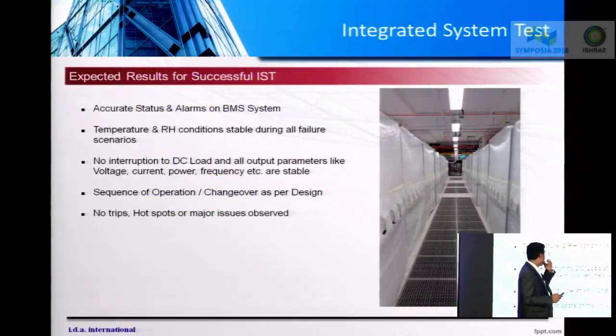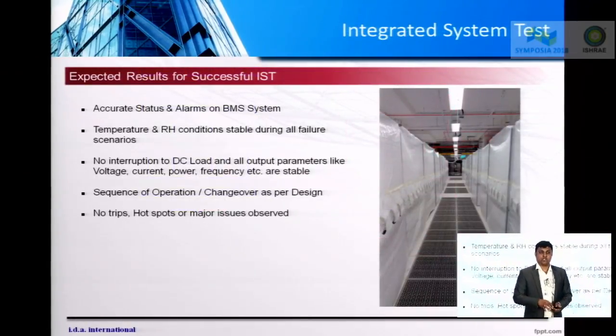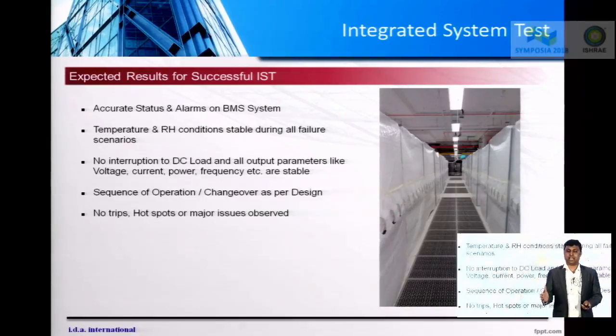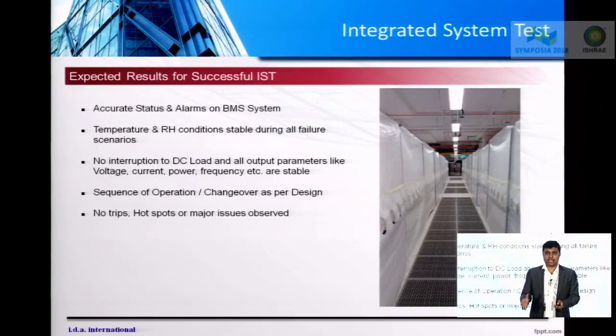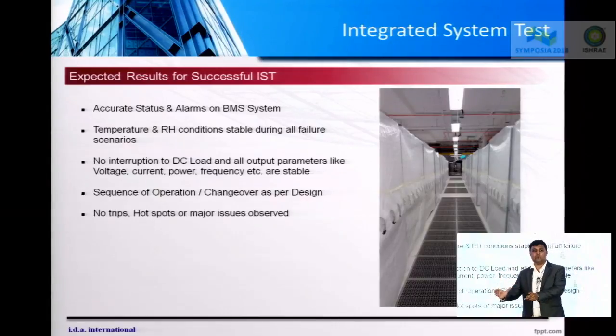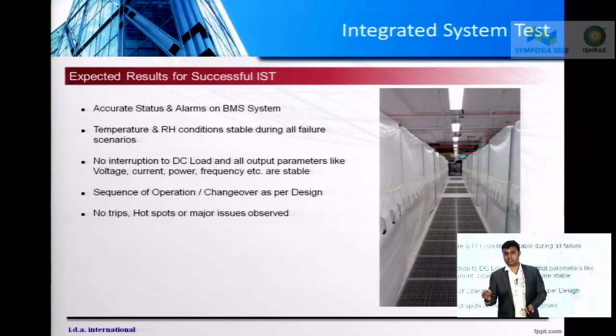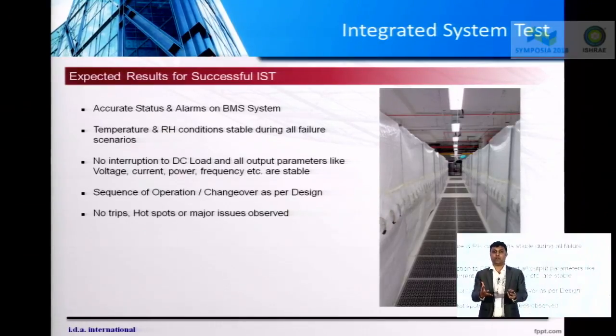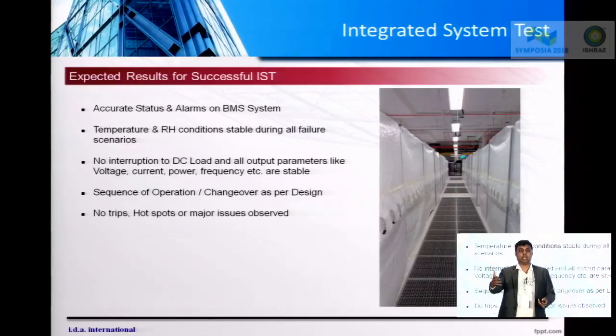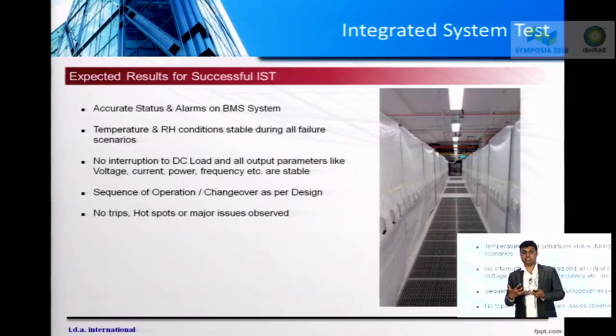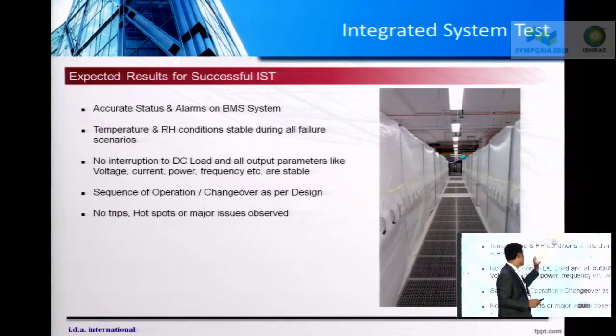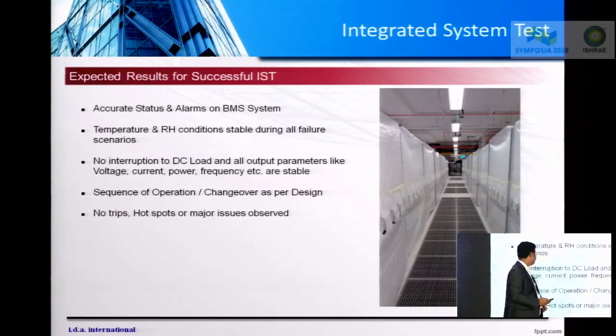So what is expected of an IST? When I'm creating so many failure scenarios, it is very important that I'm able to see the status of individual equipment and systems on the BMS, Building Management System. BMS plays a very important role in an IST. If you're not able to observe the status of any equipment, your IST has failed, because your operation team relies very much on the BMS, and whatever failure happens, your BMS should be able to get the data status immediately. Hence, we are verifying the status through BMS.